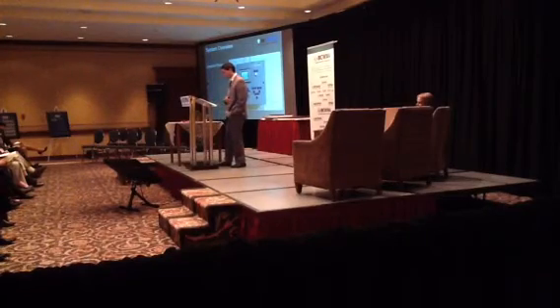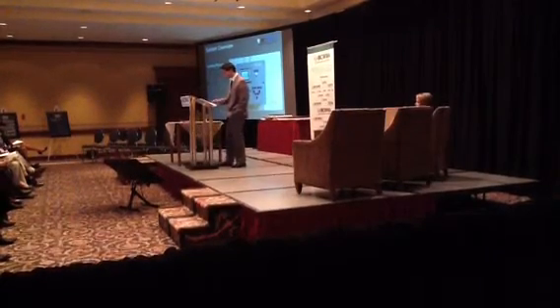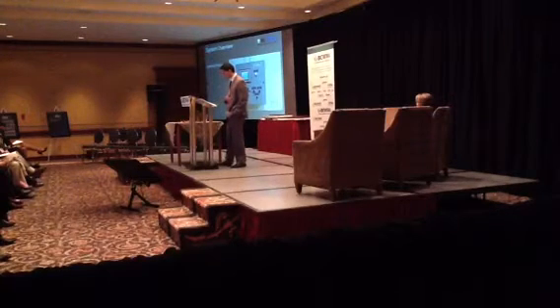The pumps can operate in a flow or head control state. Flow control is our preferred operating method as it uses the least amount of energy and provides the lowest operating costs, as pumps only increase the system pressure enough to meet actual demand. Head control state is only used in the event that SCADA communication is lost between the water transfer station and service municipalities.